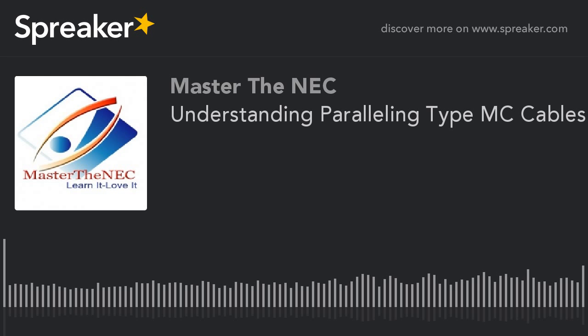So it's a 4 equipment ground, all right? So now I'm going to start that. Now I'm going to run a parallel application. Under normal circumstances, if I was running that one piece of cable, it would be 200 amps, and I have a 200 amp overcurrent device. And when I go to Table 250.122 for a 200 amp, I really only need a 6, okay?